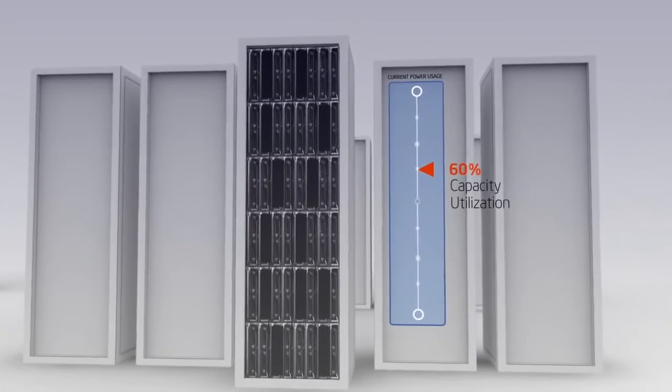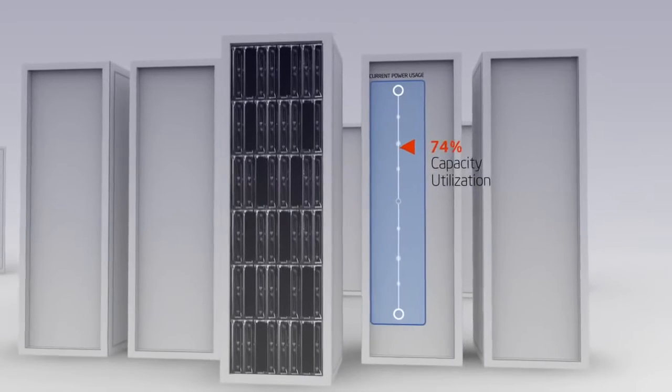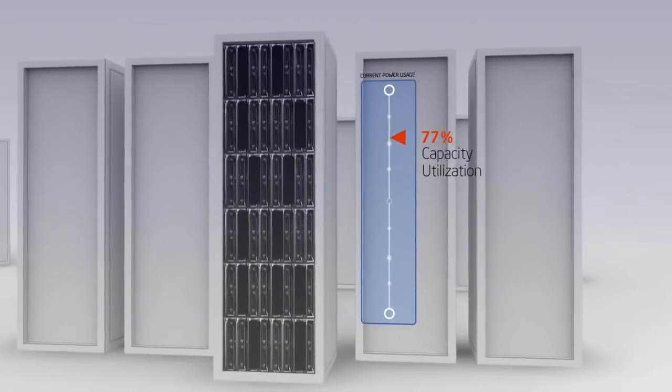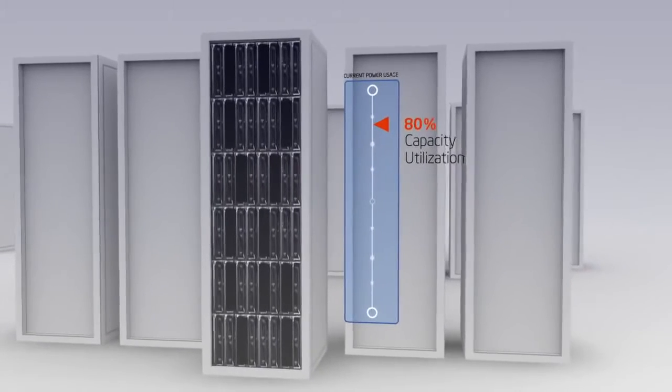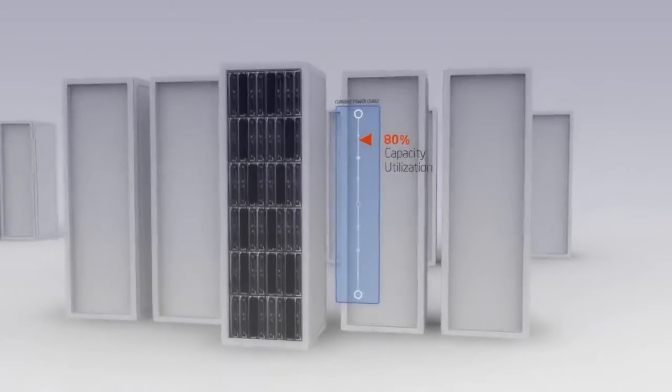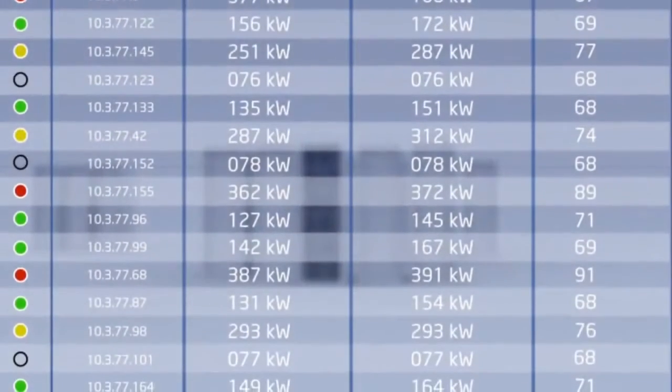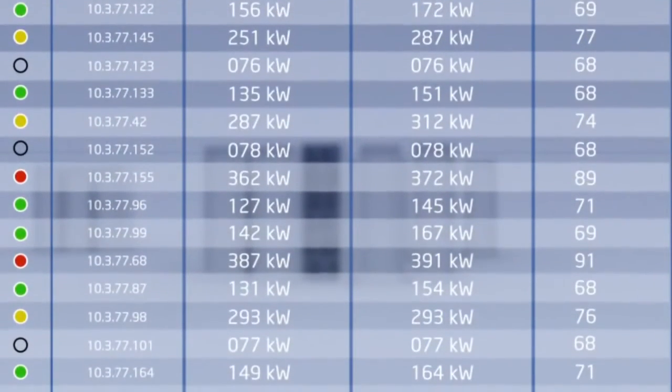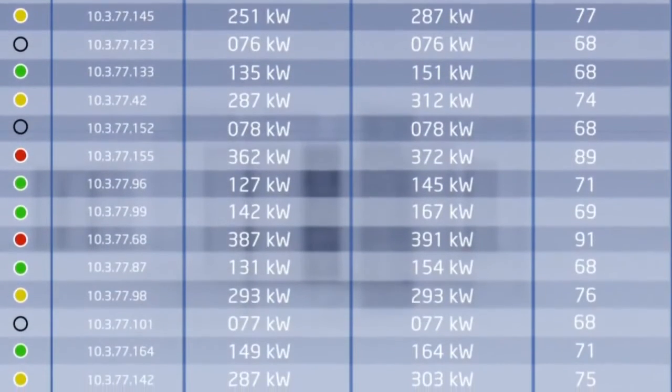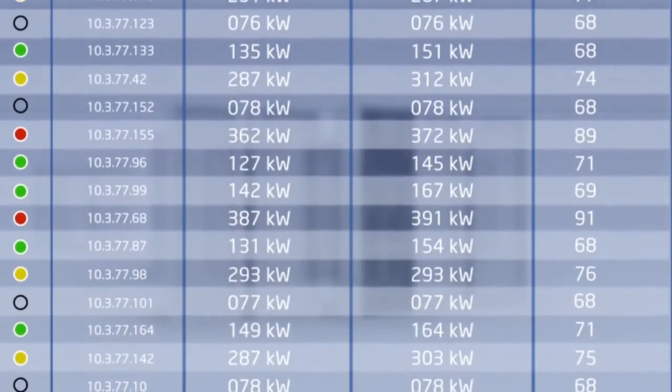In truth, most of the time, capacity planners use nameplate or derated values which are seldomly reached. Intel DCM allows you to look at real power consumption under workload, down to each individual server or set of servers. Armed with that precise knowledge, you can calculate how many units can be supported within the rack's power allocation.